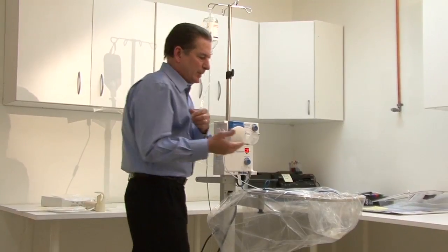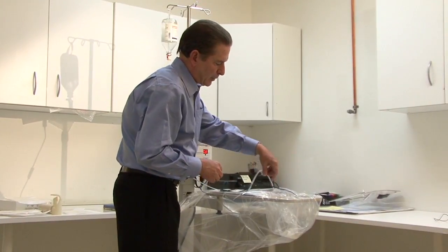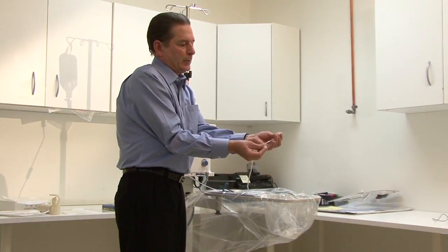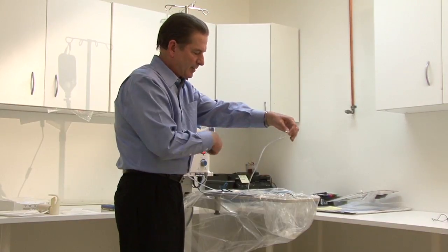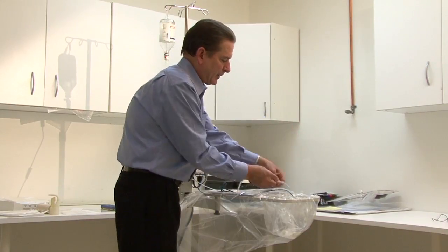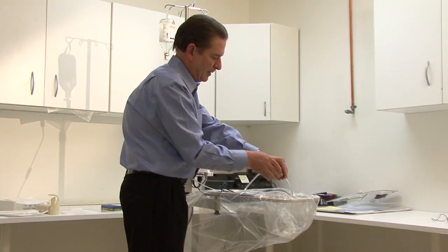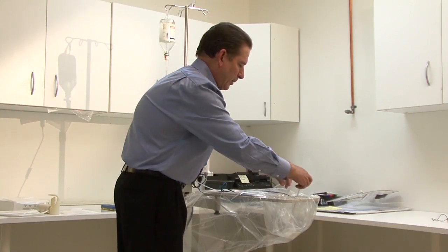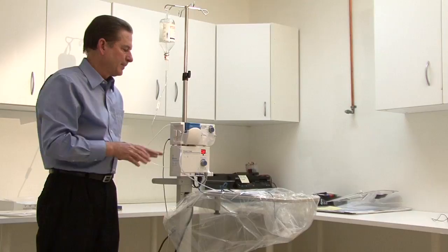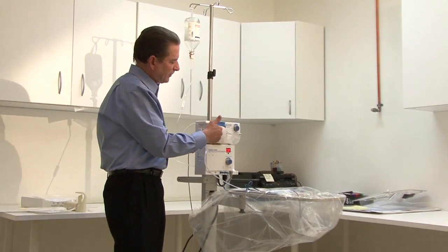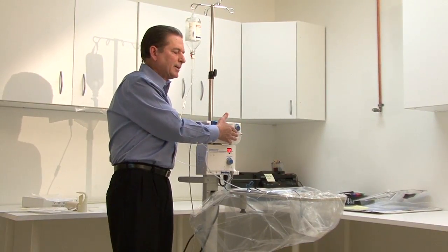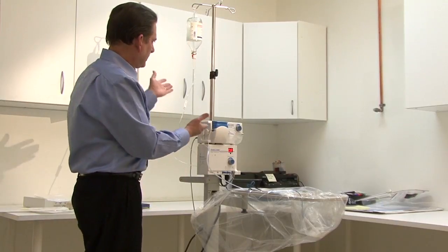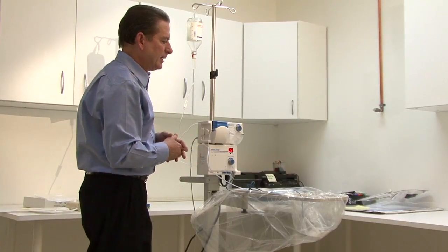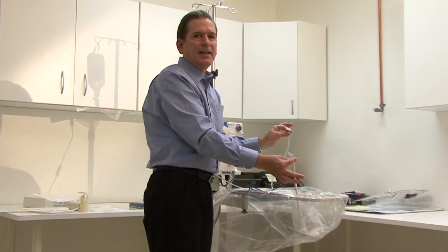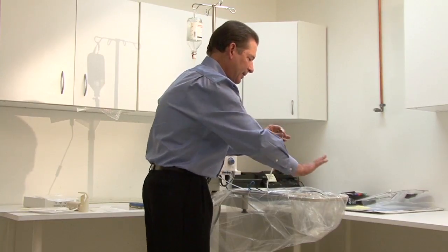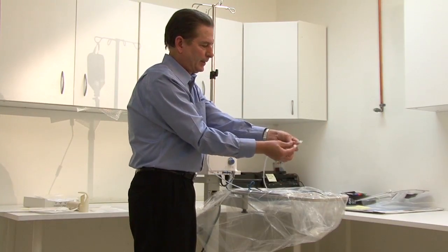Now with a lot of the equipment you use, there's different approaches. Some equipment we tend to put the irrigation aspiration lines together and prime. Other equipment we tend to connect the handpiece and run the prime that way. But with our particular Trabectome system, I mentioned that the fluid flow is very low and gentle. So the way I recommend that you set up and prime the system is start by not connecting anything. So we're just not going to connect the handpiece at all. We're going to leave this completely disconnected.